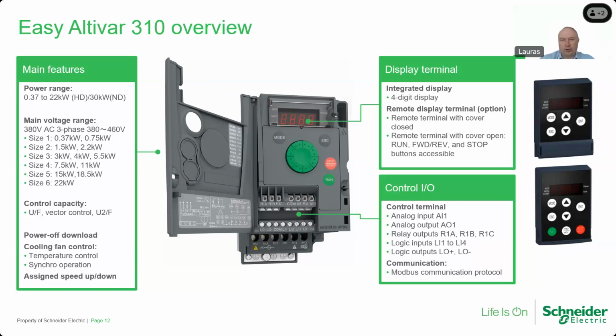It has a 4-digit display, no text display, but it also has run and stop buttons on the drive. So if you want local control, you may do it on the drive, without external push buttons. As usual, it has analog input, analog output, relay output, and digital inputs. It also has a Modbus RS485 port on board, but no possibility to add an additional communication board. If you don't have special requirements and Modbus is enough, this drive may answer your needs.